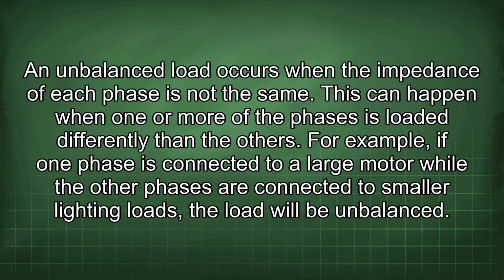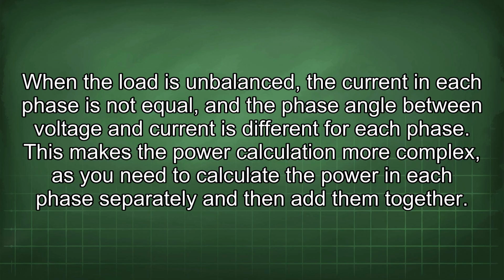An unbalanced load occurs when the impedance of each phase is not the same. This can happen when one or more of the phases is loaded differently than the others. For example, if one phase is connected to a large motor while the other phases are connected to smaller lighting loads, the load will be unbalanced. When the load is unbalanced, the current in each phase is not equal, and the phase angle between voltage and current is different for each phase. This makes the power calculation more complex, as you need to calculate the power in each phase separately and then add them together.